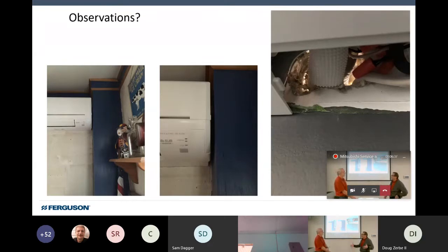Exactly. The dealer had been out 2-3 times. We had the DSGs come out, looked at this, and immediately said this is an installation issue, an application issue. The result was the dealer wound up having to disable that particular sensor, install a remote MHK controller in the room, and sense temperature from that rather than using the one built into the unit. So it cost him a returning service call, plus giving her another free controller. The whole point was it's not keeping up. It's not doing what it's supposed to.